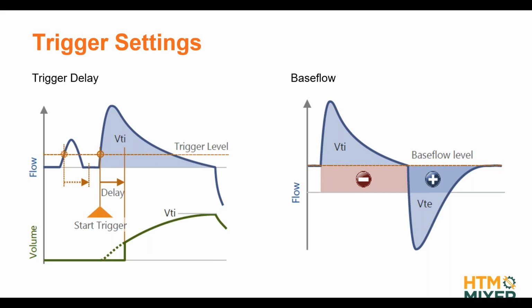And the second one is called base flow. With the base flow, you can define a flow offset that should not be considered in our VTI and VTE calculation. This could be important if you have a setting where you have a leakage that is being compensated with a base flow by your ventilator. Then you could tell the device, this is my base flow, and this should not be considered in my tidal volume calculations.